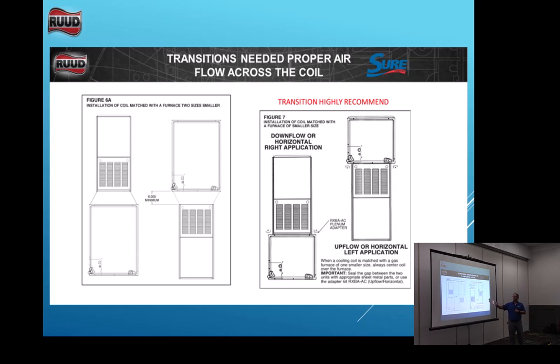But we really should have that transition. That 12-inch transition in there gives us a chance for that air to straighten out and become linear and go straight across that evaporator coil to not have any turbulent air going through it.